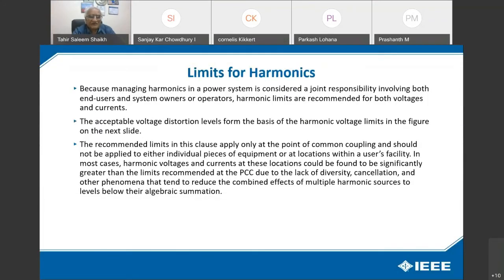Because managing harmonics in a power system is considered a joint responsibility involving end users and system owners or operators, harmonic limits are recommended for both voltage and currents. The acceptable voltage distortion level forms the basis of the harmonic voltage limit, as in the figure on the next slide. The recommended limits in this clause apply only to the point of common coupling and should not be applied to either individual pieces of equipment or at a location within a user's facility.